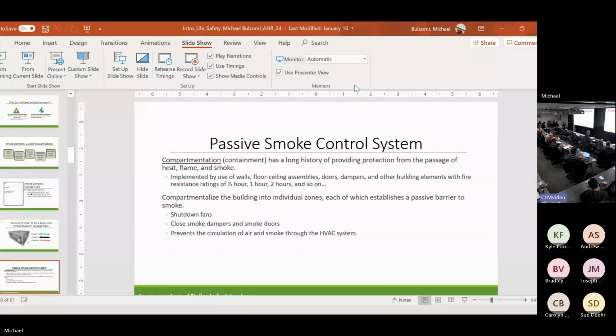So what is smoke control? There's passive smoke control and active smoke control. Passive smoke control, open and close. I'm just preventing the movement of smoke. I'm not isolating, it's not exhausting. I'm just saying there's a fire, there's smoke. Let me close this damper. Let me make sure nothing passes through this ductwork. That is compartmentation, containment. You're compartmentalizing the building into different zones. That falls under Chapter 7 of the building code.